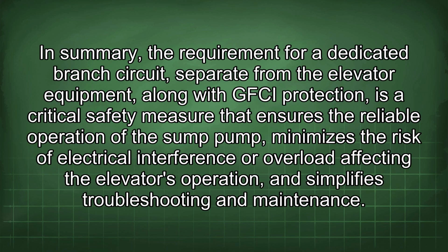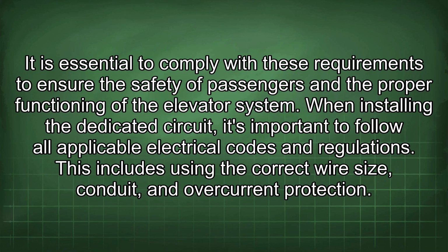In summary, the requirement for a dedicated branch circuit separate from the elevator equipment, along with GFCI protection, is a critical safety measure that ensures the reliable operation of the sump pump, minimizes the risk of electrical interference or overload affecting the elevator's operation, and simplifies troubleshooting and maintenance. It is essential to comply with these requirements to ensure the safety of passengers and the proper functioning of the elevator system. When installing the dedicated circuit, it's important to follow all applicable electrical codes and regulations.